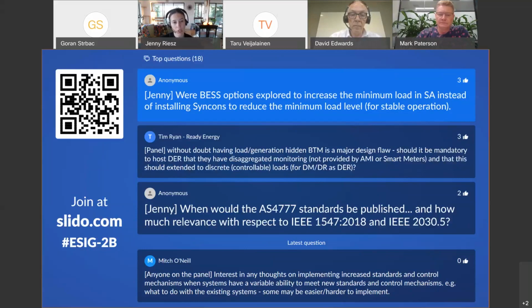In terms of using battery storage to manage minimum load, the batteries we have in South Australia are extremely valuable for minimising the amount of load needed, because they provide frequency control services very effectively. That's one of the most difficult things to manage on the island, ensuring adequate frequency control, particularly with large contingencies from PV tripping off.